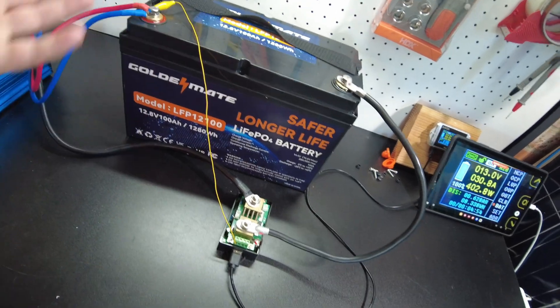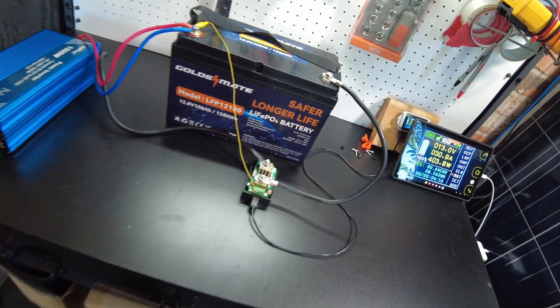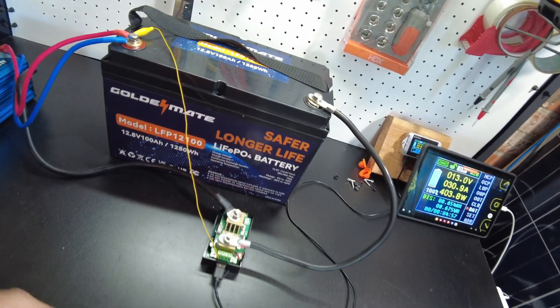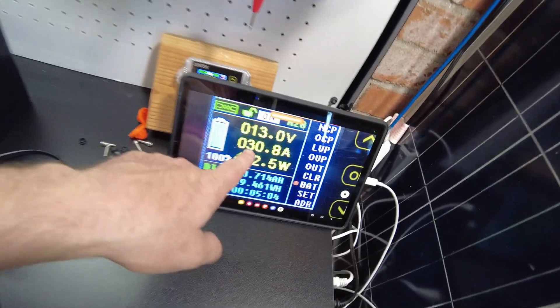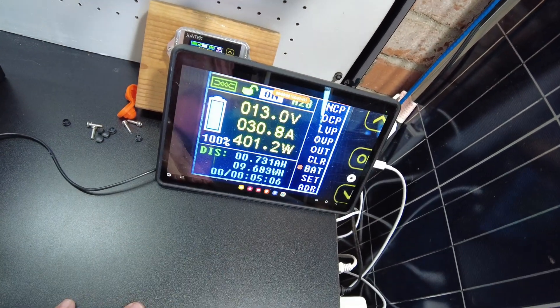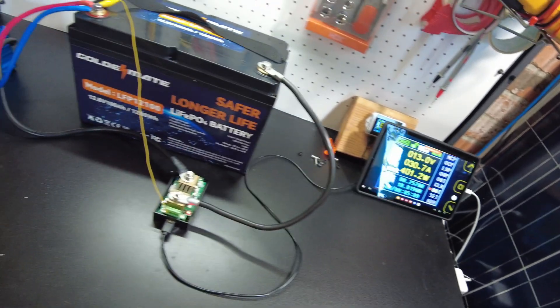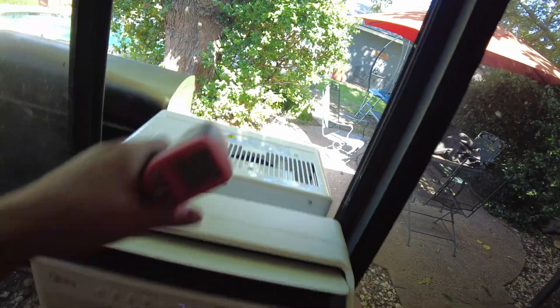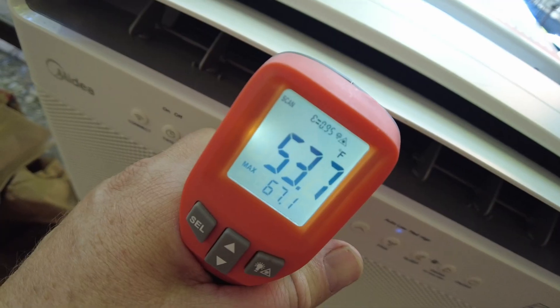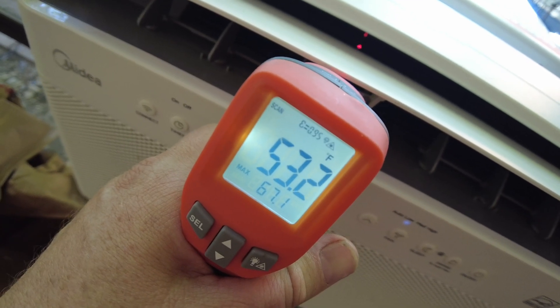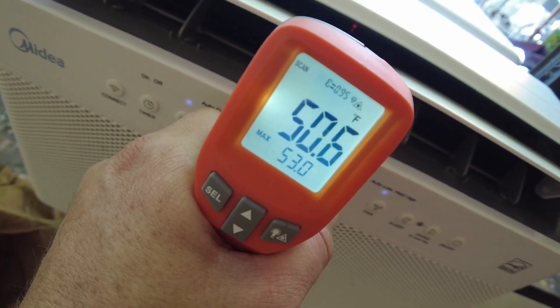But if you watch my discharge tests, I usually go well over that. I usually go for a 0.5 and even sometimes a 1C discharge test. I haven't seen much of a difference between a 1C, a 2C, or a 5C when it comes to this lithium iron phosphate chemistry. And if it fails at 30 amps, which is just slightly over 0.3C, we'll rerun the test and give it another go. Yes, I know I have a big hole right here. I've got to cut out a piece of plywood. I've got 53 degrees coming out of there.